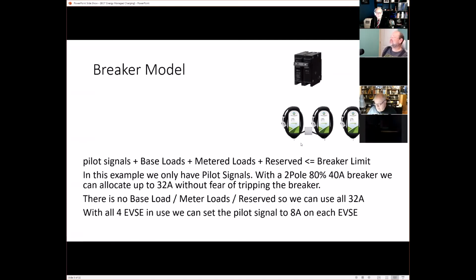So in this example, in this picture I showed, we have 4 EVSEs. We can put all 4 of these EVSEs behind a single 40 amp breaker, and we can offer 8 amps to each car if all 4 were in use. We could put 6 chargers behind this 40 amp breaker as well. But with these chargers, with a minimum of 8 amps, it would mean that only 4 could be getting power at a time. So it's not impossible to have 6, but you start having to shuffle power around, saying, turn these two off for the next hour, and then turn those on, turn 2 others off for the next hour. And so you end up shuffling through the things. And I would prefer not to do that. I know Don Chandler has been a big proponent of going up to 6 if that's all the power requirements people have. And we haven't gone down that road to really see that in action yet.